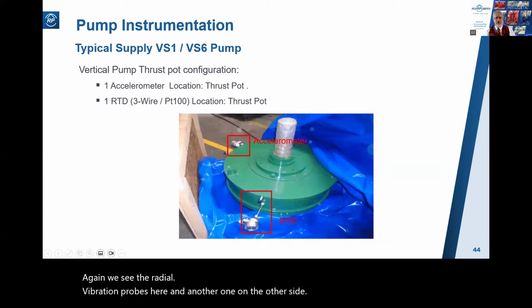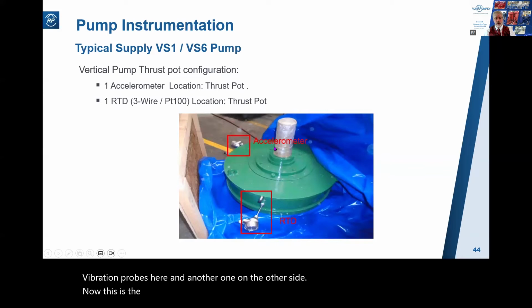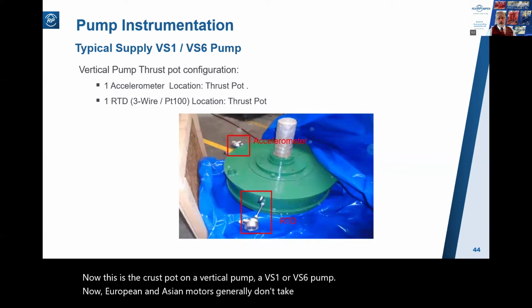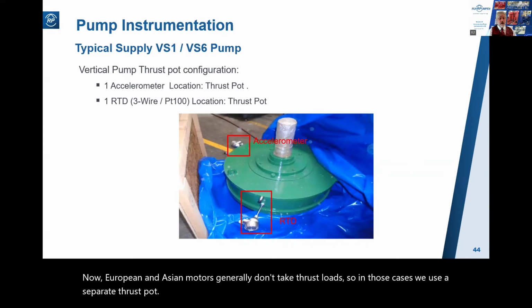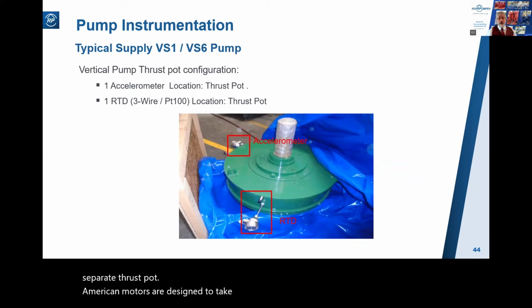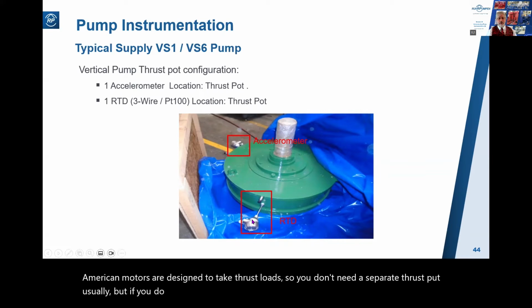Now this is the thrust pot on a vertical pump, a VS1 or VS6 pump. Now, European and Asian motors generally don't take thrust loads, so in those cases we use a separate thrust pot. American motors are designed to take thrust loads, so you don't need a separate thrust pot usually. But if you do have a thrust pot, here's where you'd measure the RTD and your accelerometer.